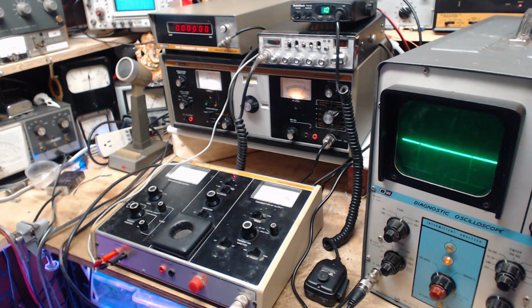26 megahertz oscillator adjustment. Now 26 megahertz. What's this all about? The actual frequency is 26.255. So they're using this frequency to mix with the output of the radio you're testing to produce a 1 megahertz difference frequency, which it then produces at a terminal you hook up to your oscilloscope. So while your radio is transmitting 27 megahertz, this thing's converting it to 1, so you can put a lousy cheap oscilloscope on it and see it. An oscilloscope that maybe only goes to 5 or 10 megahertz. Doesn't go all the way up to 30. So you cannot see the output directly. That's a pretty attractive feature. Back in the day, it's a pretty attractive feature.